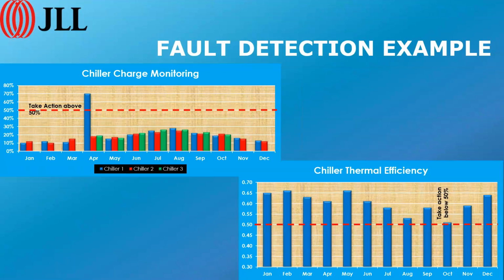I generally will say that if that number is between 2.7 and 3, then you know you have a chiller charge problem. And there's no magic way around that problem. If you don't have enough gas in the system, the evaporator is going to become starved because it's trying to cool down the system enough, and the evaporator pressure is going to drop off. It's going to get lower and lower, and that delta P number between high side and low side is going to get bigger and bigger, and you're dividing it by the evaporator pressure, which is getting smaller and smaller. So it creeps up pretty quick. And that is a sure sign that you have a refrigerant problem.